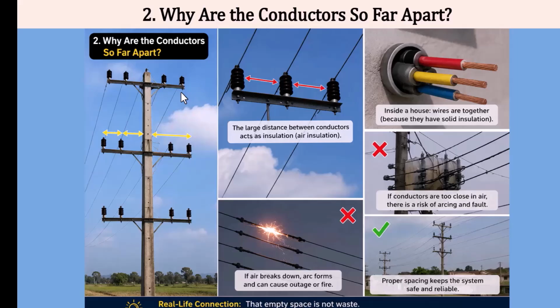So, physical distance means part of the electrical insulation system. Now imagine bringing two conductors at significantly different potentials closer and closer. The electric field in the gap becomes increasingly important. If the electric stresses become high enough to exceed the dielectric strength of the surrounding air, the air can break down. Then an arc may form.